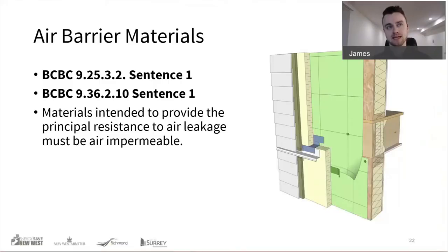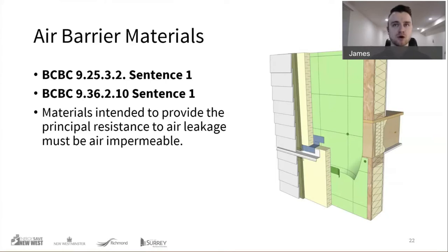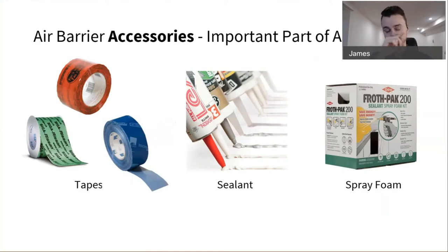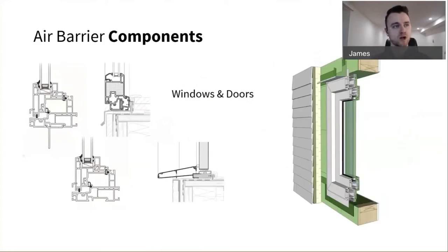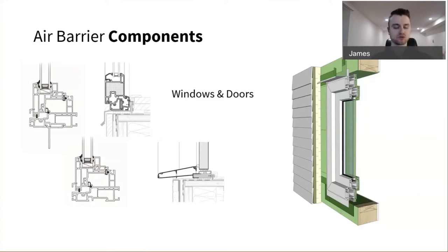BCBC 9.25 and 9.36 both have different definitions about the air barrier itself — materials intended to provide the principal resistance to air leakage. But it's not just the sheathing membrane. It's a combination of all the accessories and components: tapes, sealant and spray foam, plus the components themselves. Windows and doors going into our walls need to be correctly airtight and sealed properly at the perimeter. We're reviewing the entire enclosure from top to bottom: roofs, ceiling planes, floors as well.